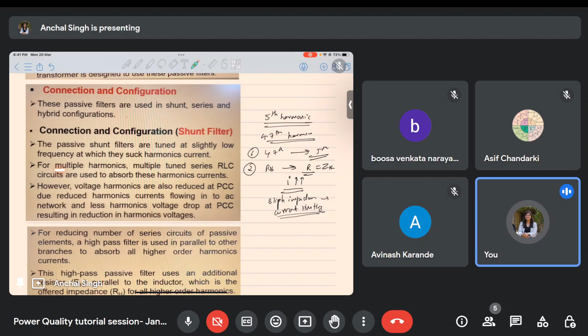So in order to limit that current, instead of tuning at exactly the fifth order, we tune it at slightly different from the fifth order, so that we have slight impedance in the circuit which will limit the current. So for the current limiting purpose, we are doing this. In practical conditions, instead of designing for that particular harmonic, we design at a slightly lower harmonic order. Okay, and if my system has multiple harmonics, then we could go for multi-tuned filters.